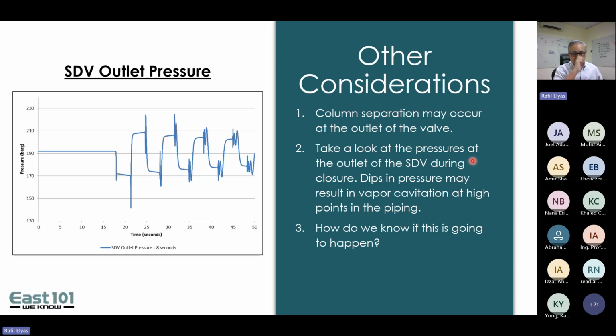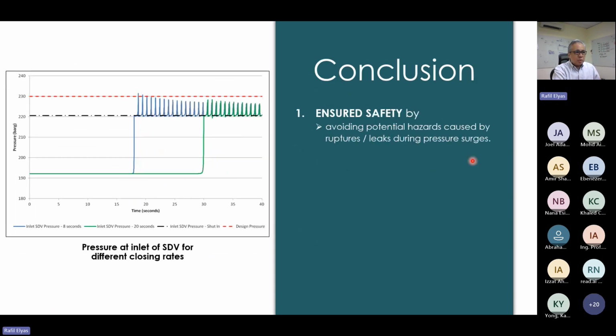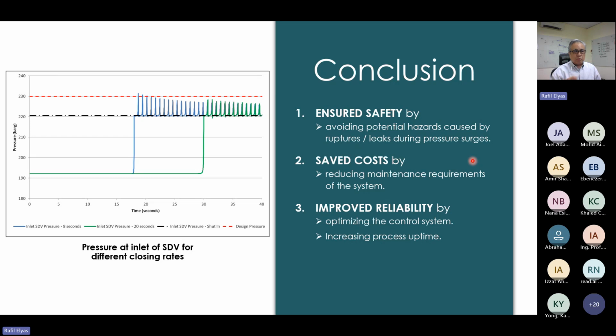So how do we know what's going to happen? Well, again, we built our simulation using something like PipeNet or AFT Impulse. On PipeNet, you can track cavitation to different degrees of rigor. If you use these kinds of transient single-phase liquid systems, you get to avoid a lot of these hazards, save a lot of costs, reduce your valve cavitation, make sure that you can have proper startup, reduce equipment vibration, etc.